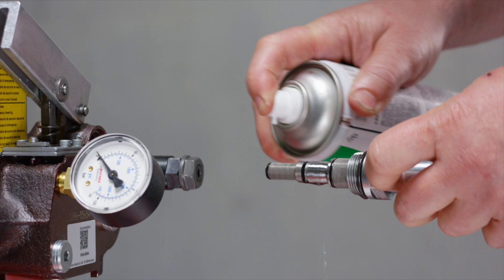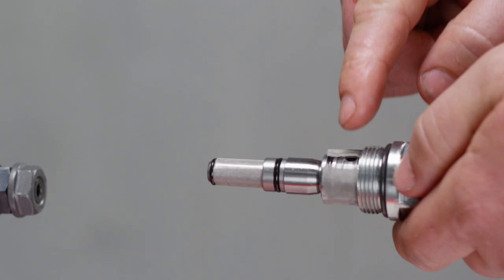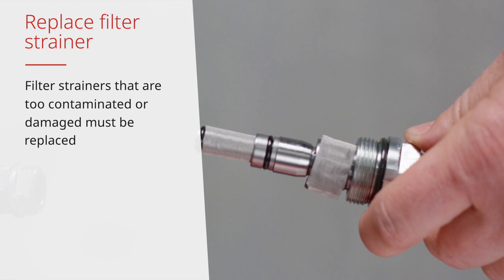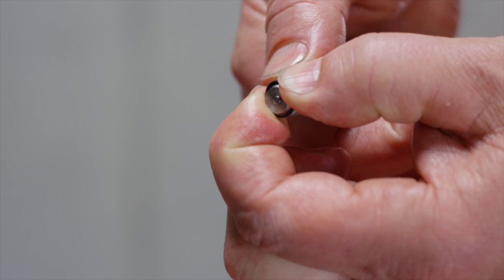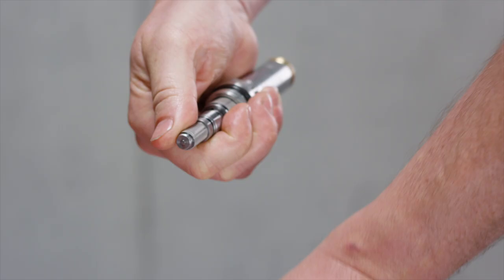Filter strainers that are too contaminated or damaged must be replaced under all circumstances. Pinch the O-ring between the tips of forefinger and thumb and push them to the side. Push the O-ring off the pilot valve with the thumb of the other hand. Pull the filter strainer off the pilot valve.